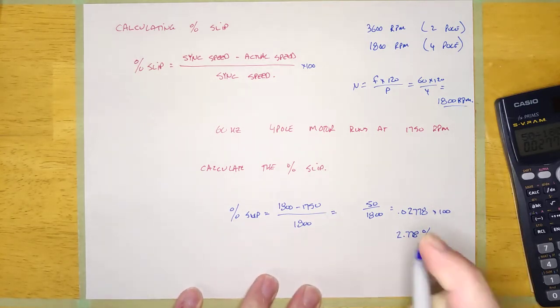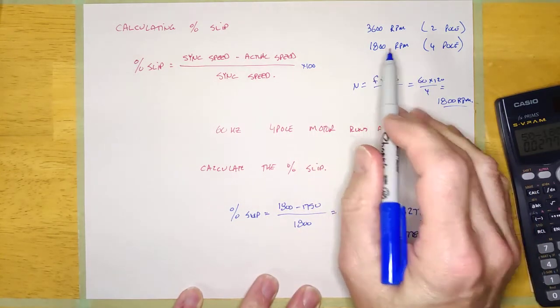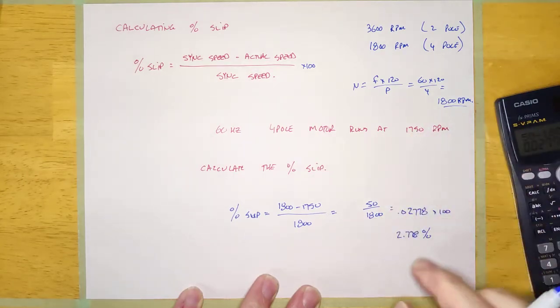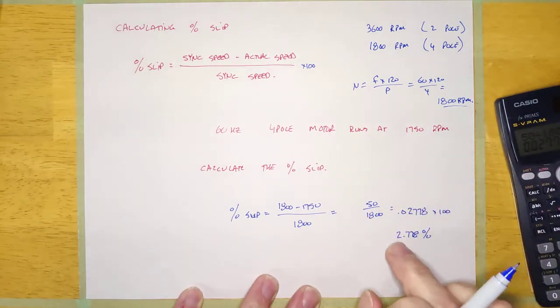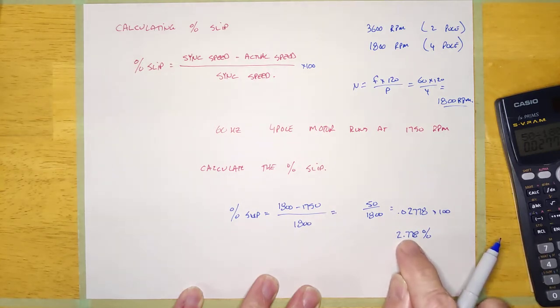Because at no load, it's going to be running at really close to 1,800, very close. And at full load, it's going to be running at 1,750. And that range is 2.778%. And so if you look at a motor, the lower the percent slip is, the better the motor is, really. It's going to have a more constant speed.